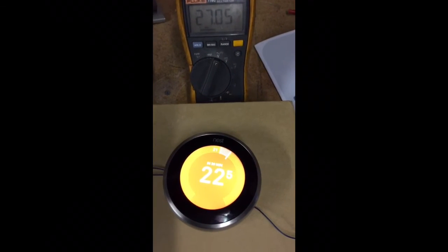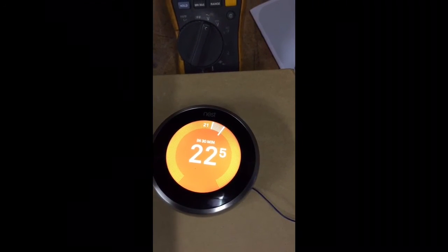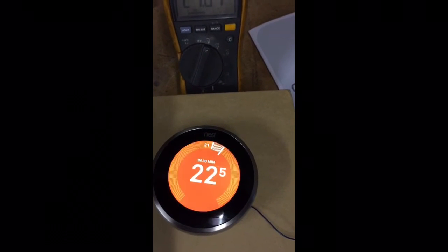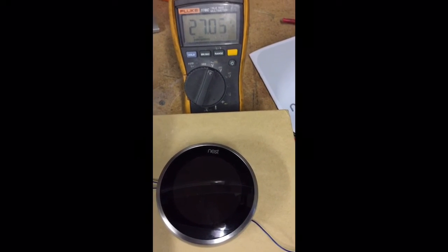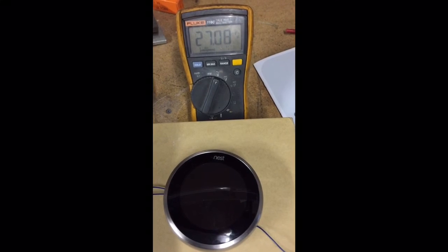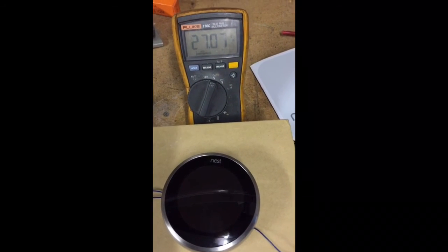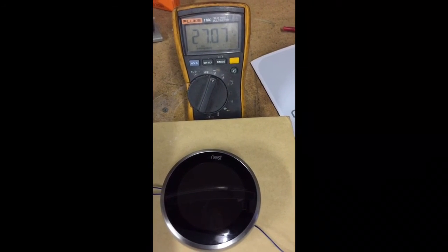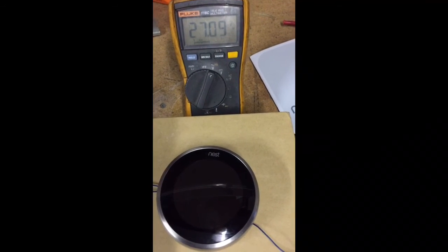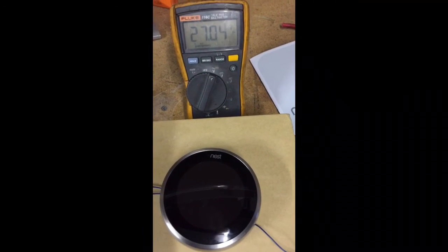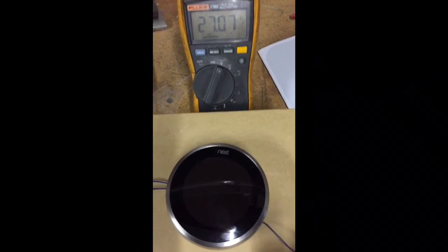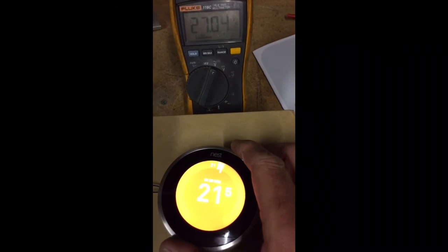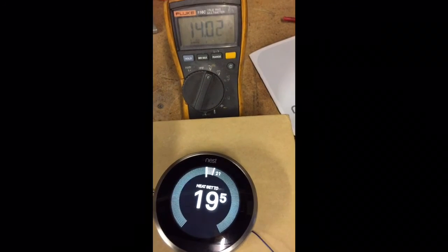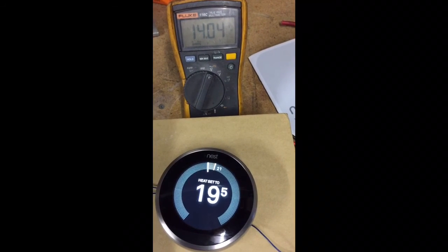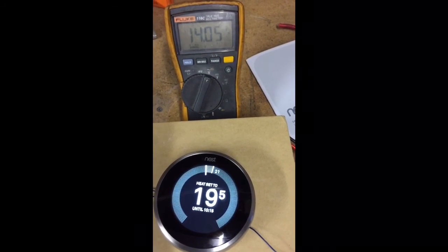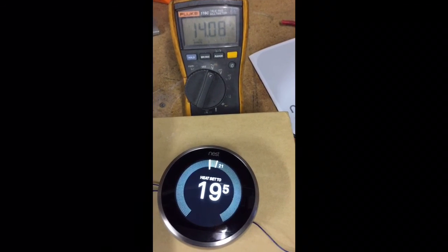If you have a look at the screen on there, it says in 30 minutes. So it's got a 30-minute override, and after that 30 minutes, the system will revert back to its programmed mode. That's just a manual override we've done for a short period of time. The screen has now gone into a sleep mode to preserve the battery life. If we want to adjust it back down, it's just a matter of touching the screen and winding it back down, and there we're in the off position again, back to 14 volts, which like I said is that residual voltage.